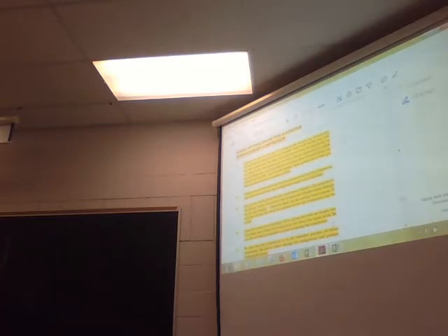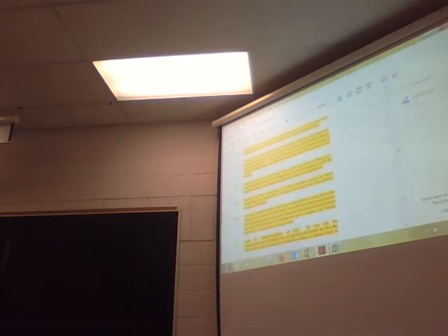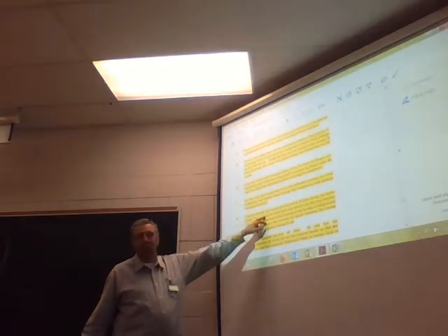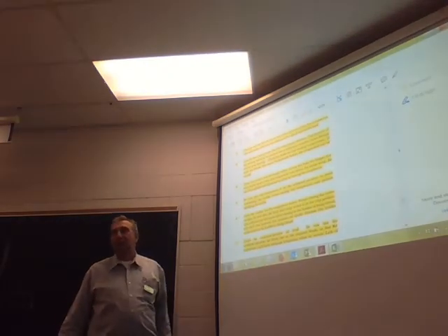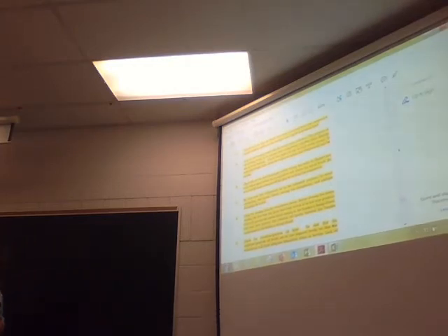Be sure that the compressor is in the unloaded position. You don't want to start up a compressor under load. You want to make sure it's unloaded. If you start it up under load, you could do some damage to the motor. Close the breaker for the compressor motor. Before closing the motor breaker, be sure the local stop-start switch is on. So before you put power to it, make sure that the local stop-start button has been pulled out.